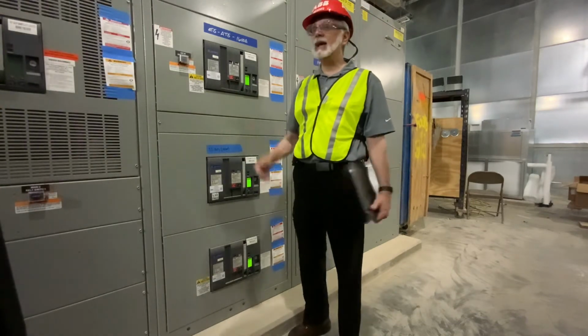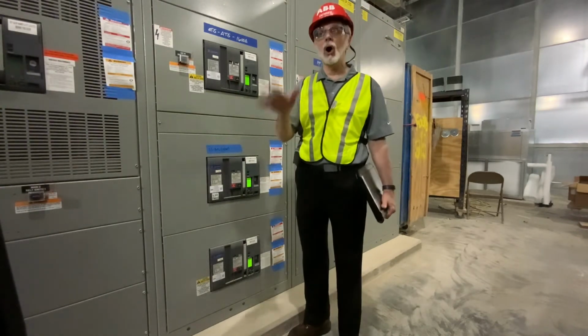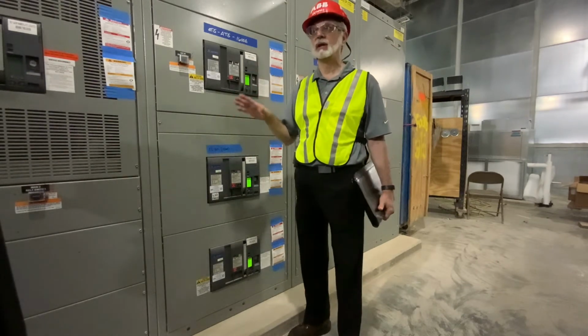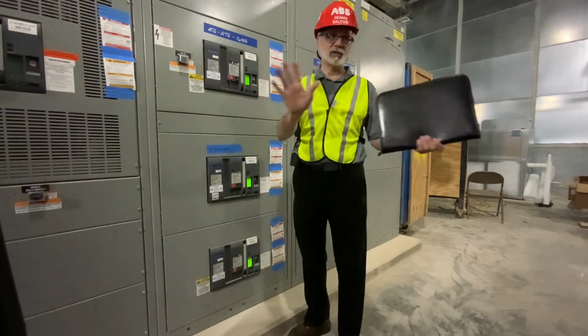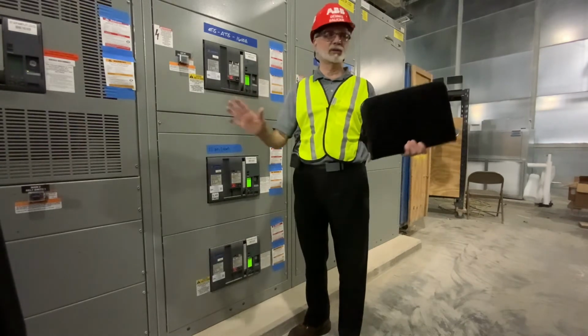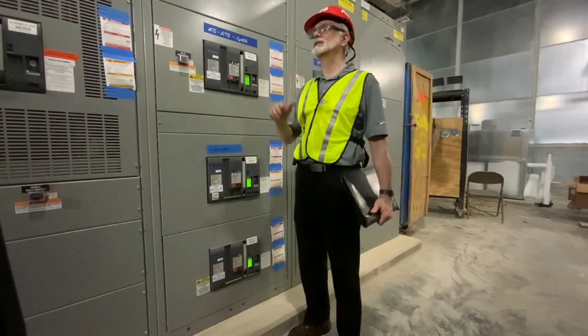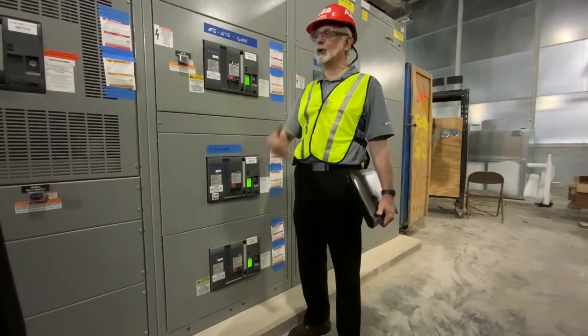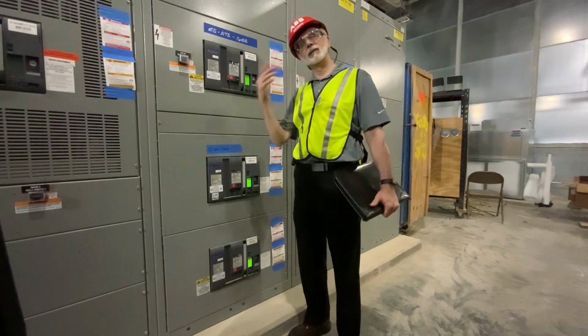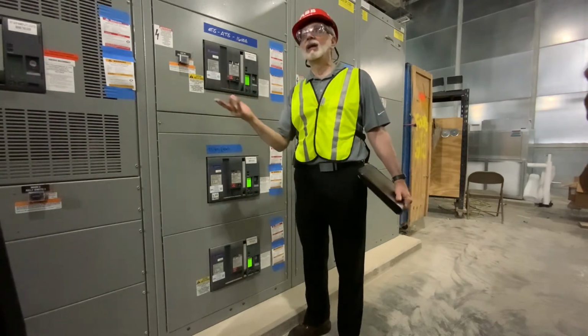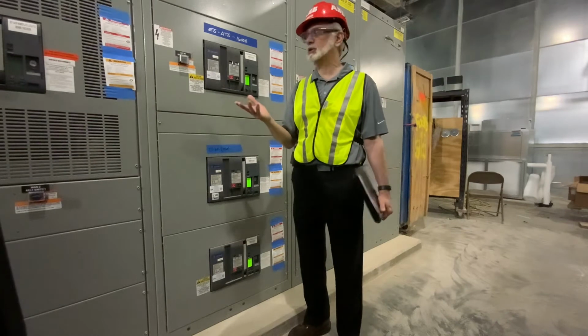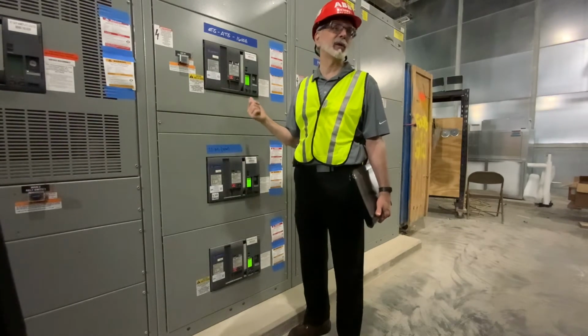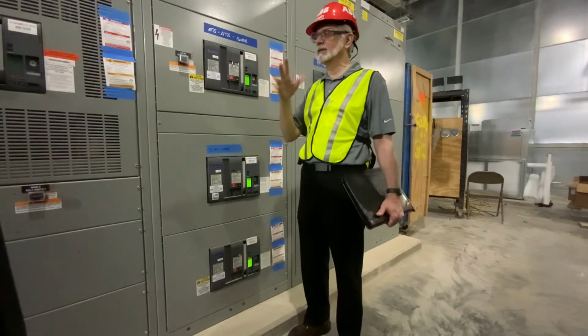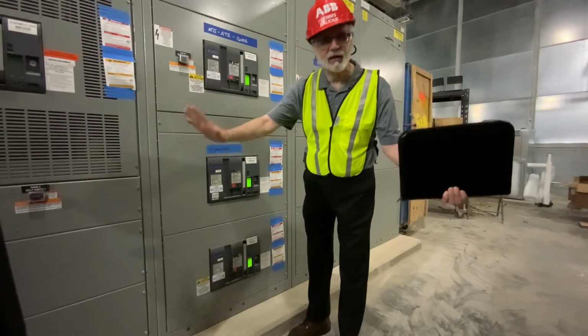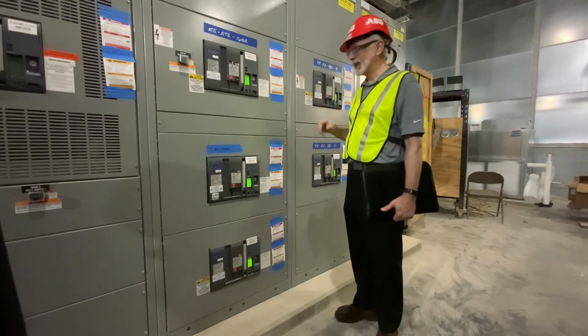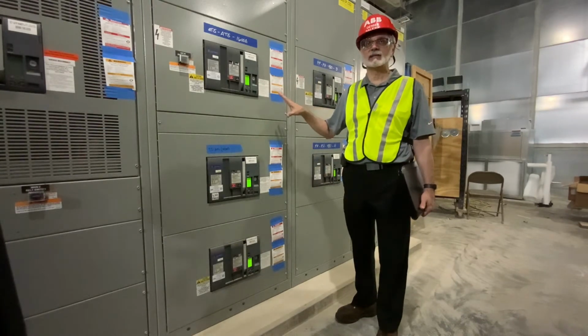Again, there's no harm in leaving the springs in the charged situation, but it's up to you. I'm not telling anybody how to run their breakers here. I'm just telling you there's nothing wrong with leaving the breakers closed in the charged position. From a safety standpoint, I could see where it might be an advantage to leave them in the discharged position, mainly because these are draw-out circuit breakers, and even though there's an interlock, it's personal preference. Whatever you like is fine. Any questions on the feeder breakers associated with this?